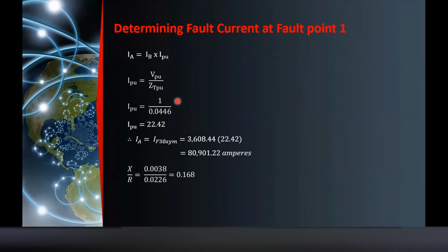Okay? So 1 per unit divided by the total impedance per unit at the faulted point, which is 0.0446, you will get 22.42. Okay? So balik ka ulit dito sa formula na to. Sabi natin na yung I actual, I fault 3-phase symmetrical, is simply 3,608.44, which is the same as my secondary full load current, multiplied by 22.42, you will get 80,901.22 amperes. This is my fault point 1, symmetrical.